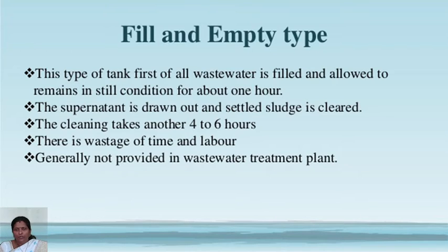Now see one by one, the fill and empty type. In this type of tank, first of all, wastewater is filled and allowed to remain in still condition for about 1 hour. The supernatant is drawn out and the settled sludge is cleared. The cleaning takes another 4 to 6 hours. There is a waste of time and labor, so it is generally not provided in wastewater treatment plants. In older days, this method was adopted.